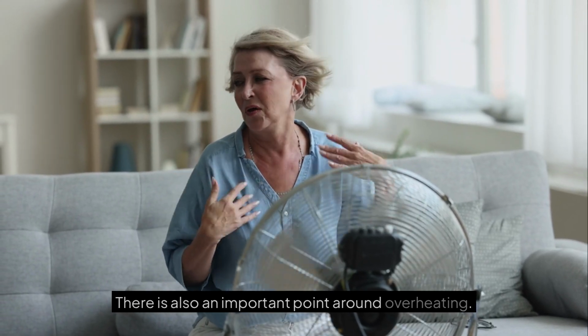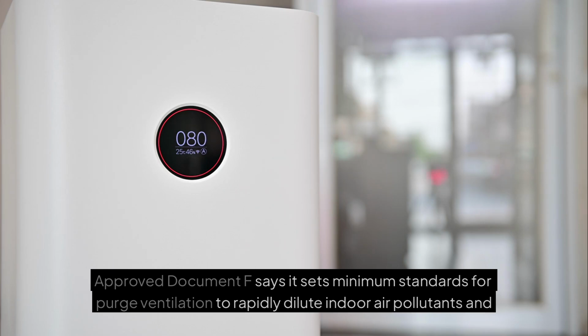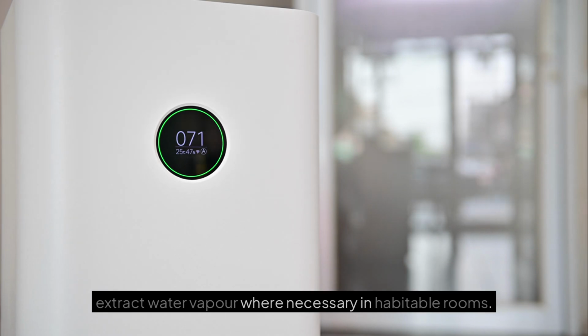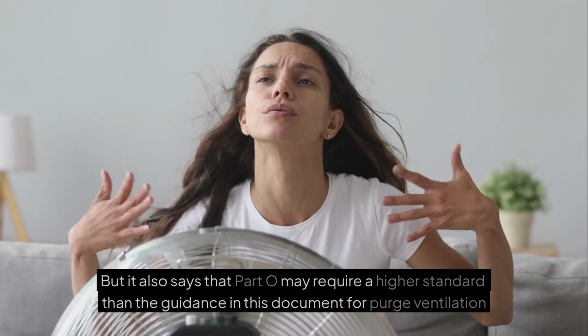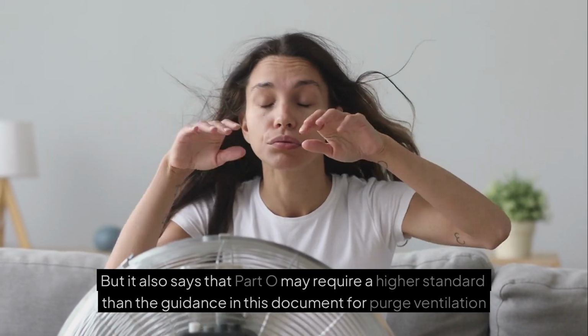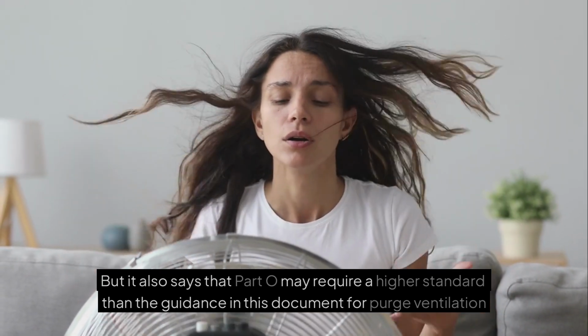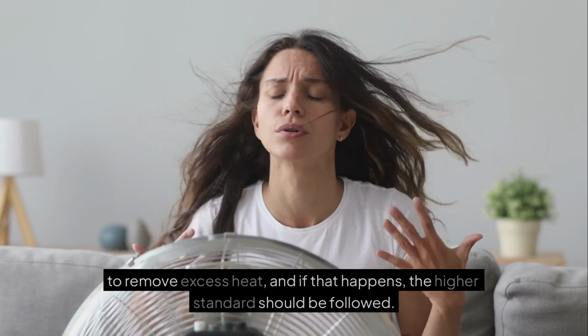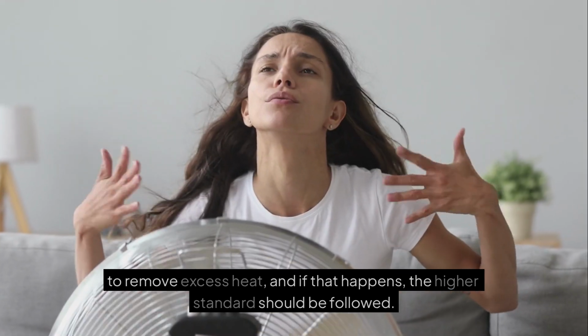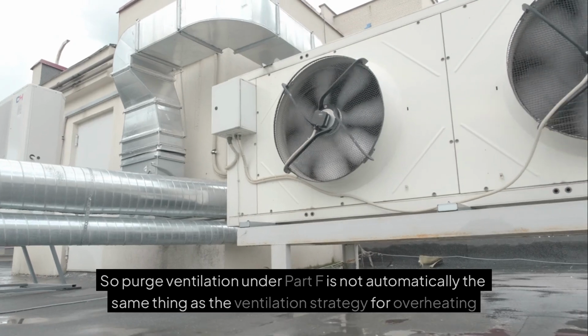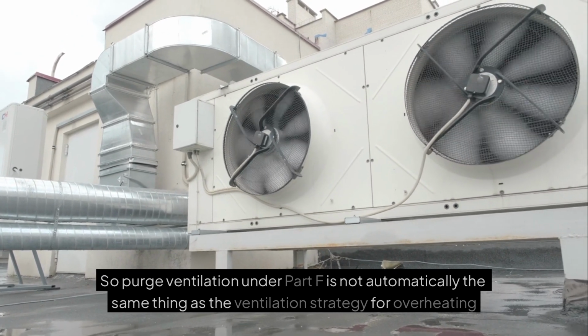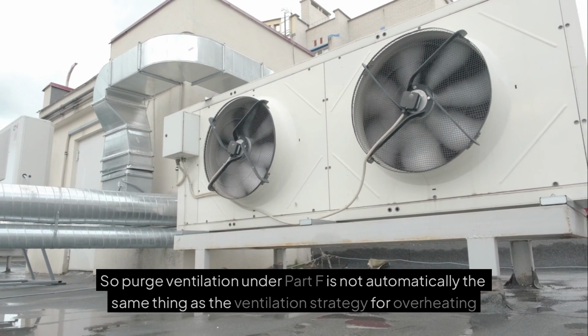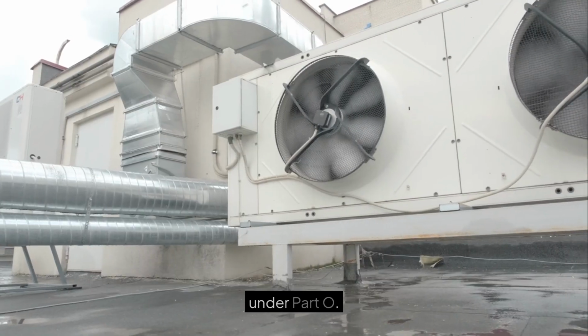There is also an important point around overheating. Approved Document F says it sets minimum standards for purge ventilation to rapidly dilute indoor air pollutants and extract water vapor where necessary in habitable rooms. But it also says that Part O may require a higher standard than the guidance in this document for purge ventilation to remove excess heat. And if that happens, the higher standard should be followed. So purge ventilation under Part F is not automatically the same thing as the ventilation strategy for overheating under Part O.